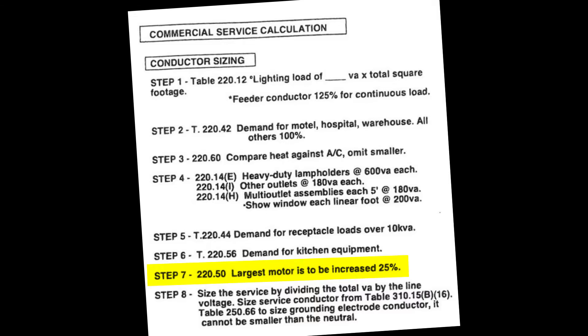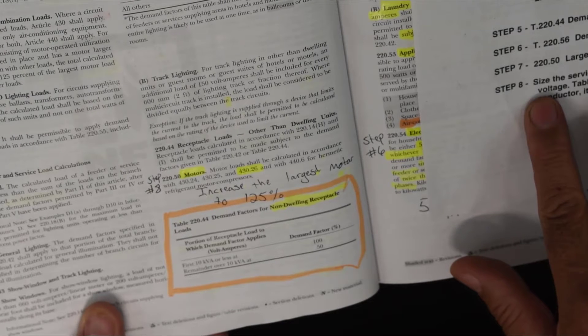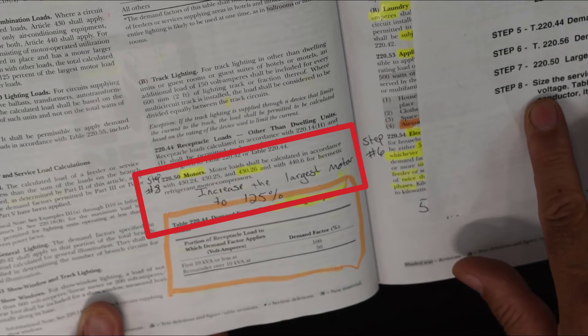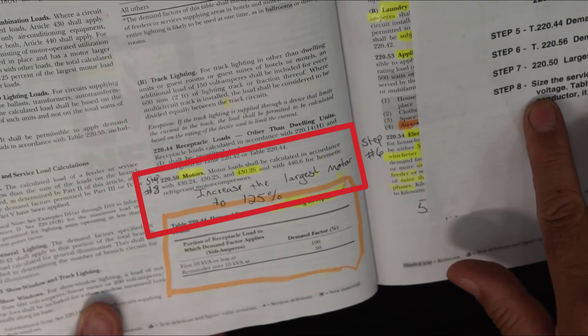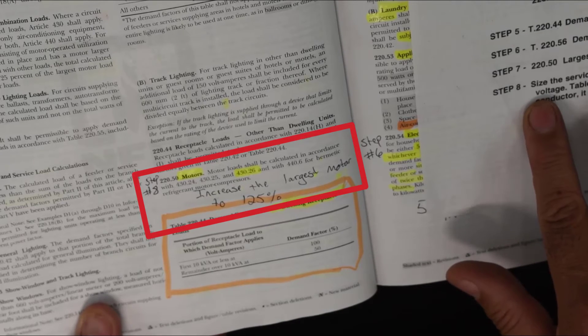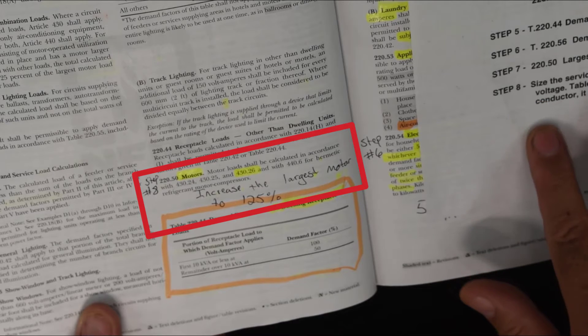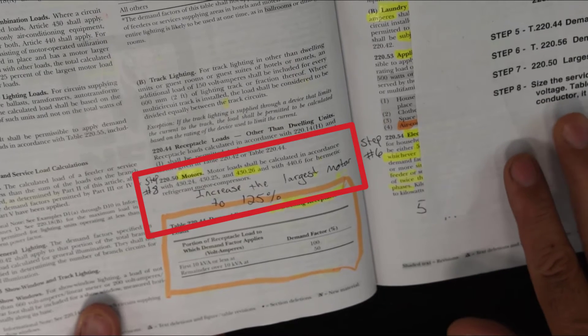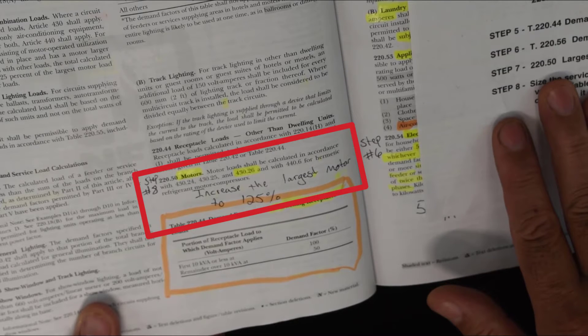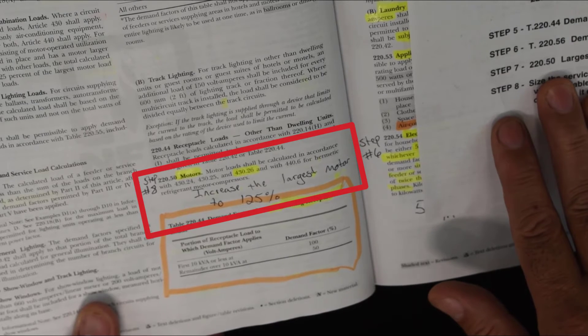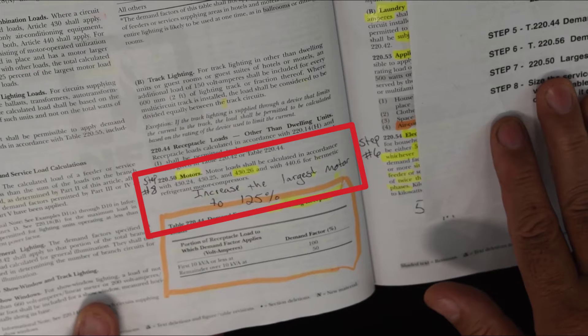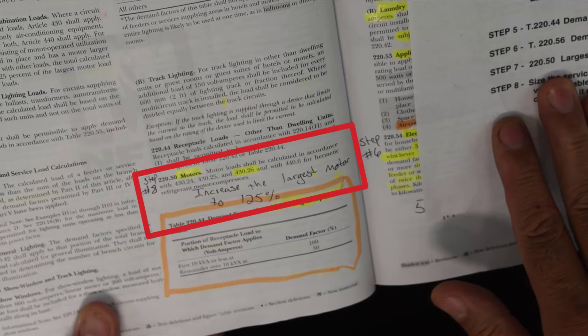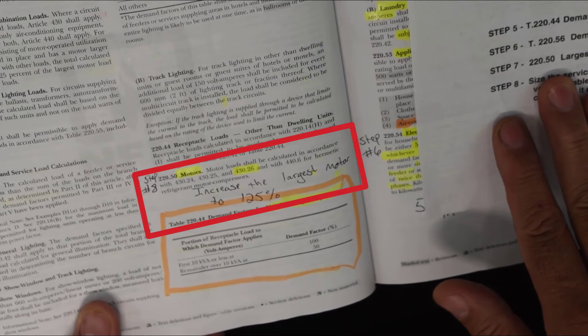Step 7 addresses the largest motor. We increase it by 25%, just as we did for the dwelling unit. This takes us to Article 430.24, 25, and 26, which tells us to increase the largest motor to 125% of full load current. Since we already have 100% of that motor included in our tally, at step 7 we simply add an additional 25% of the largest motor's full load current to our running total.